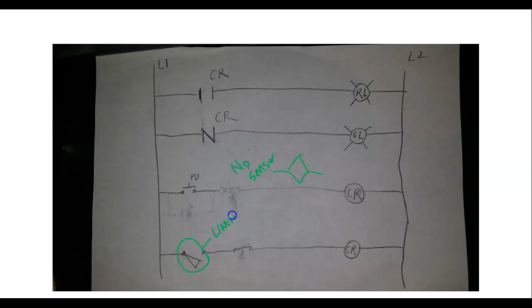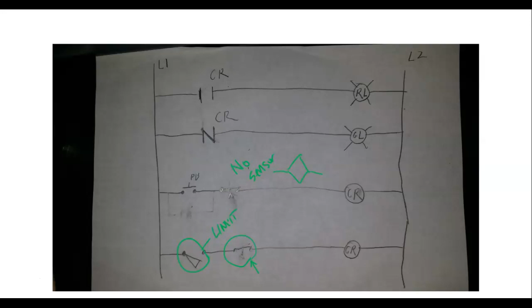So they've got a limit switch here, but there's no call for a limit switch in the whole design project. Oh yeah, I see what you said - they tried to put a timer contact here, but they have no timer coil. We just can't put contacts for timers without having a coil that controls it, right?